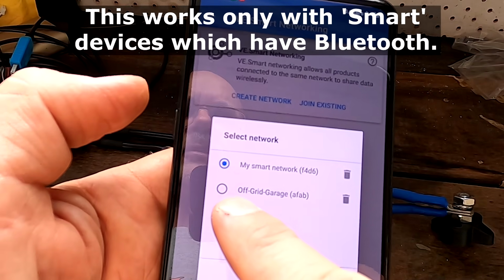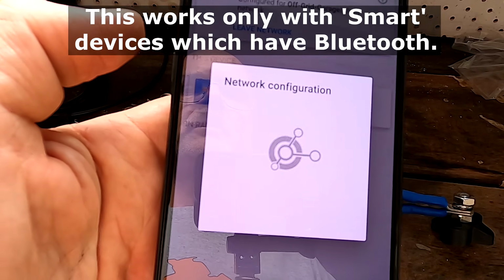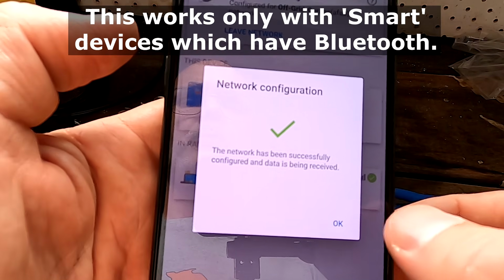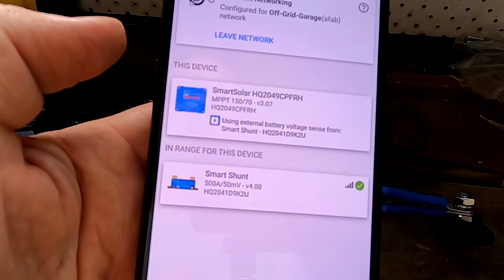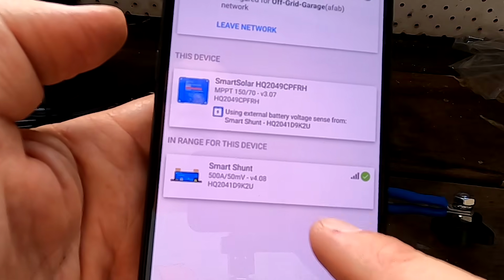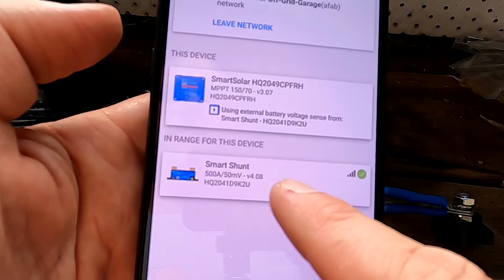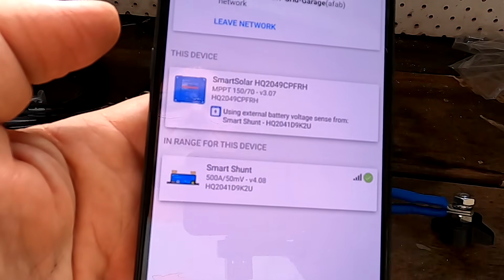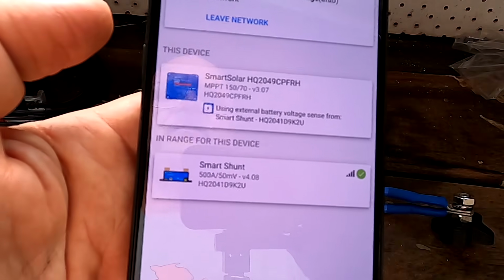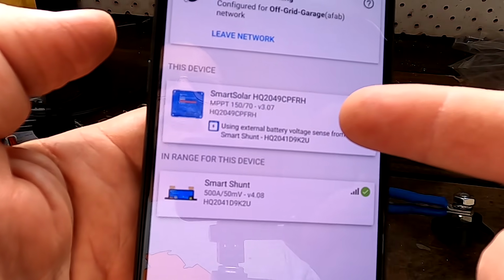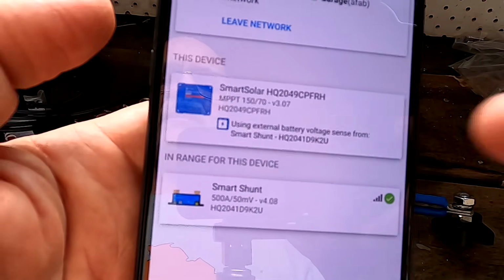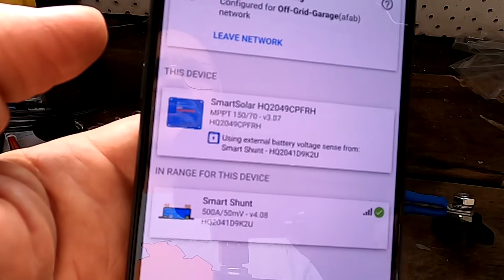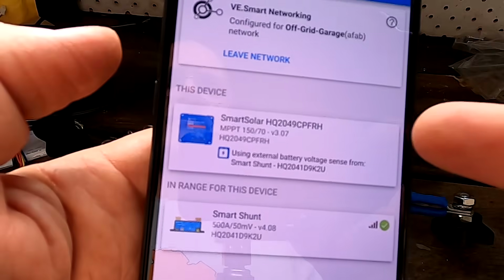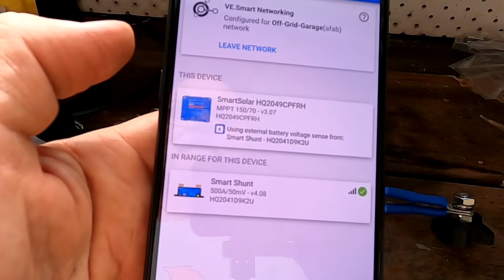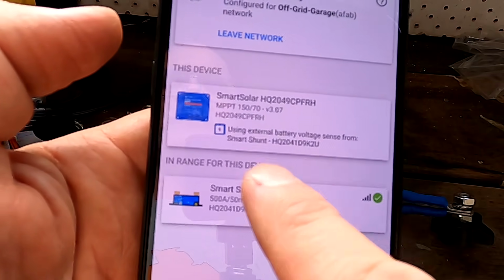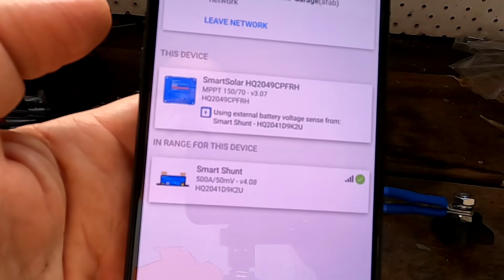Join existing — the off-grid garage is already there. Network configuration connects the charge controller with the smart shunt now. See, they are in a network and talk to each other. The smart shunt actually measures the voltage far better than the solar charge controller because it's close to the battery, and it gives all that information to the charge controllers. If you have more than one charge controller, you link them all together in this network, and if you change the settings in one, the others will follow. So one is always the master and the others are slaves — even if they don't show the changed parameters in their own settings, they just do what the master says, which is correct, this is what you should do. It also says it now uses external battery voltage sense from the smart shunt — see, they're already communicating, and this is how it should be.